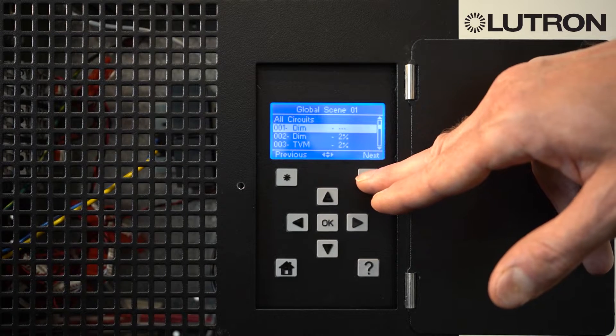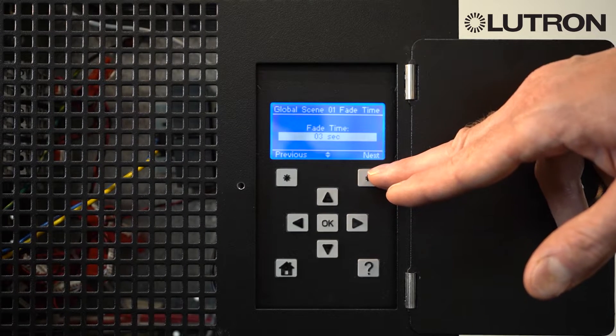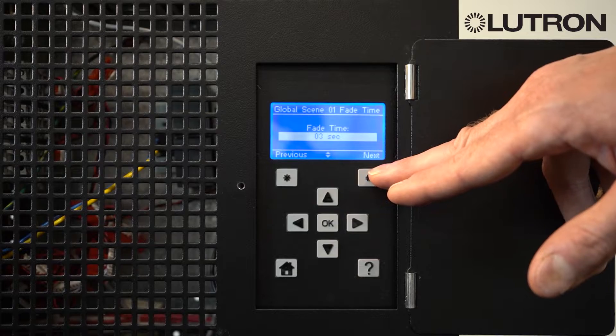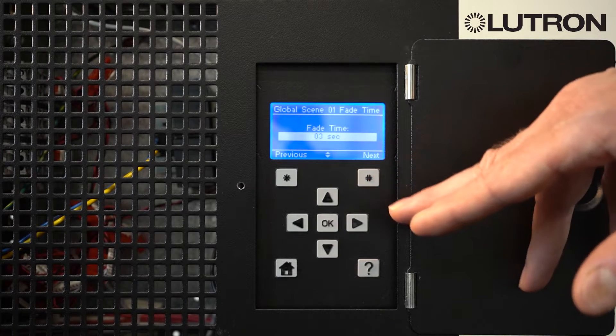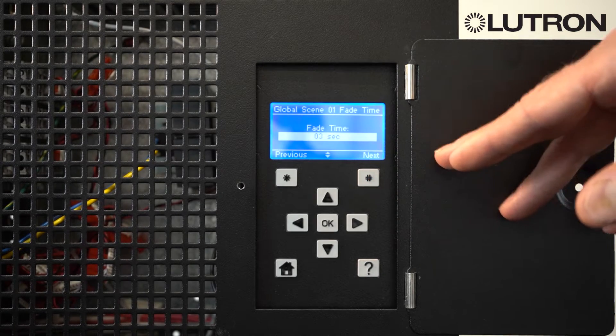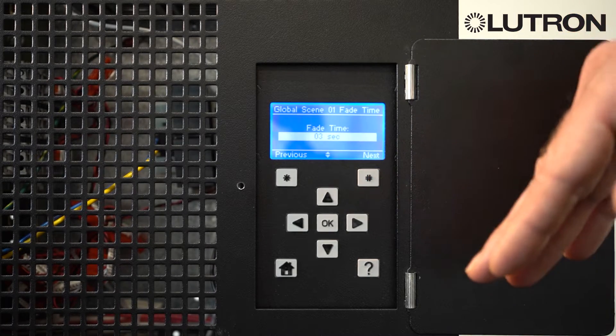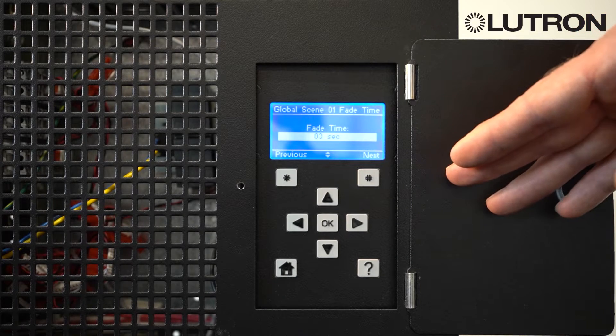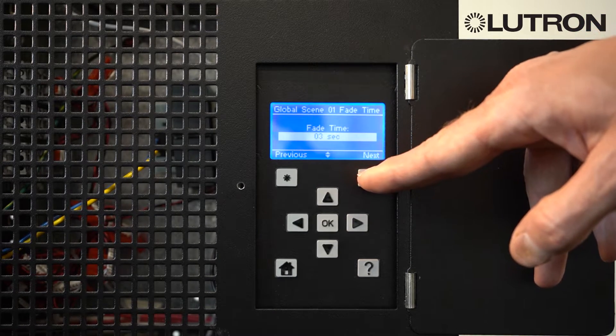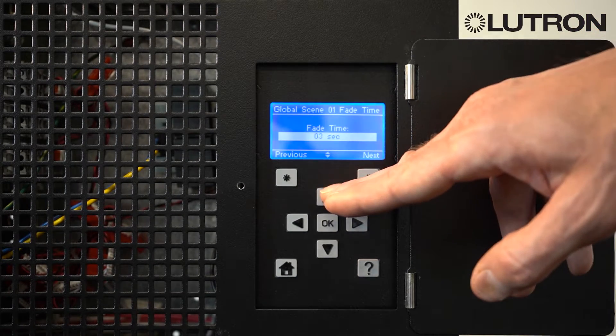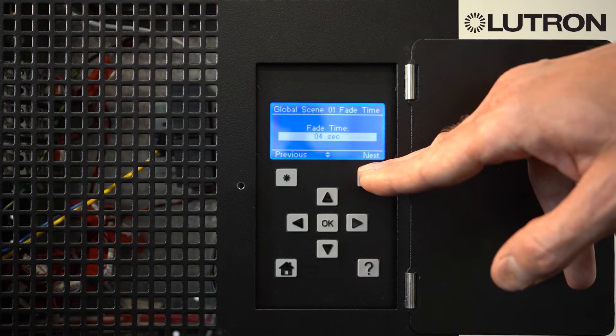When you're done, press the Next button. It will then ask you the fade time. The fade time is the amount of time it takes for the lights to reach the desired level after pressing the button. Longer fade times are often less noticeable in spaces. The default is three seconds. You can modify the fade time and then press Next.